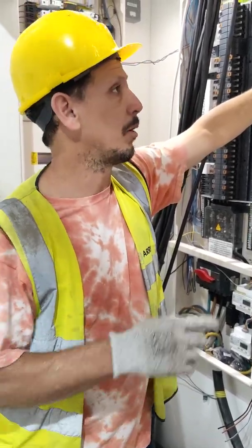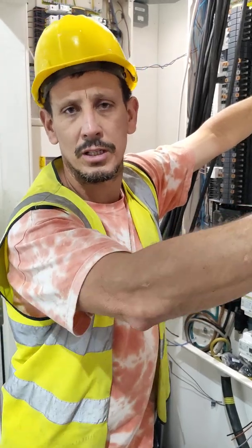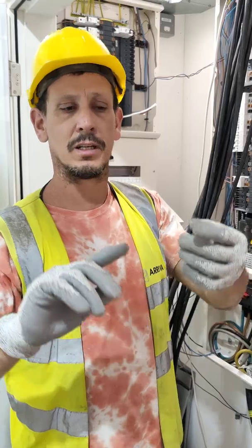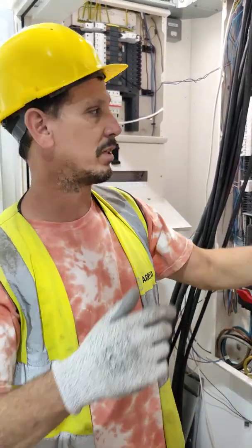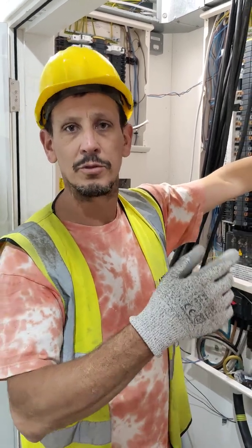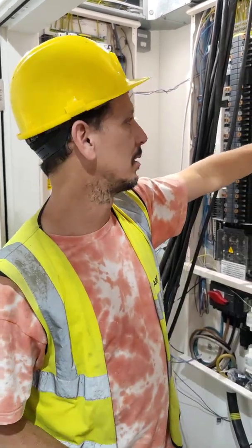So after all the installations are put into place, the sockets, the switches, we'll go to the far end, if it's a radial or a ring, and we'll twist the wires, and then we'll come over here and do a bell test, which is for continuity, and then there will be a few more tests that need to be done, the live test.